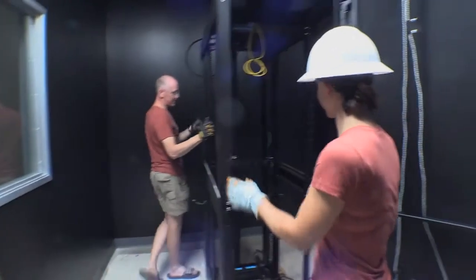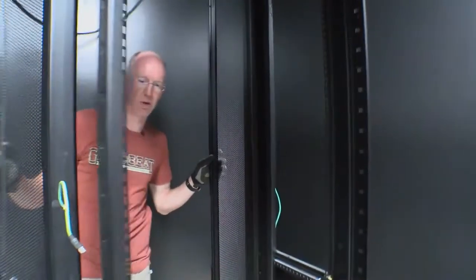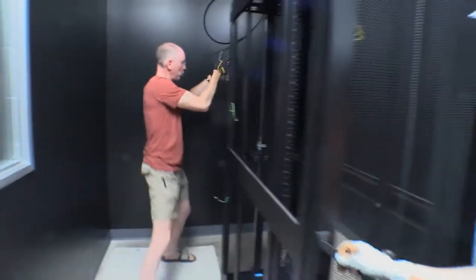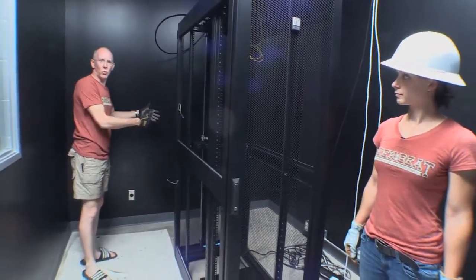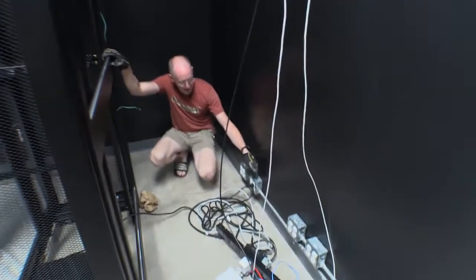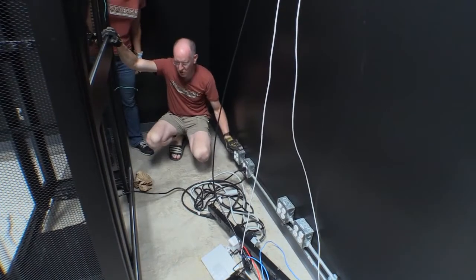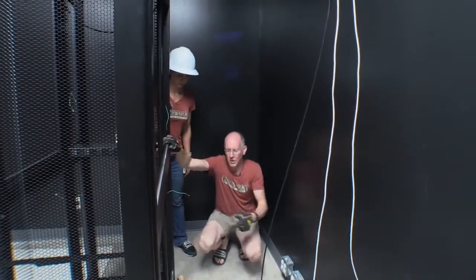What's also cool is the back of these racks has a different kind of door system — it's a split door. The reason you'd want a split door in the back instead of one giant one is because when these racks are all in this room, they'll be lined up this way. We'll leave lots of room in the front to open the doors but it'll be closer in the back. We've got multiple power here — enough for three different racks, which is what Chatsworth sent us. Each one is on a different circuit to a separate battery. Two batteries and two power strips for redundant power throughout all of the racks.